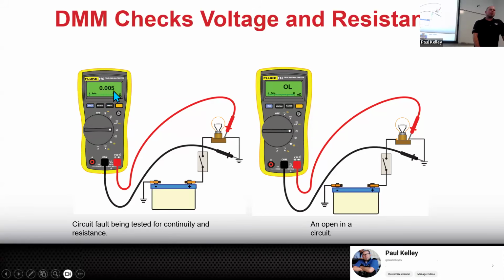So if you look at this, that's pretty much 0. You've got not a tenth, you've got a half of a nothing there. That wouldn't even show up typically on the meter, so you're good - that has 0 volts after. Coming into it, you should have source voltage of 12.6, and we'll show that, but this would be using the meter to check available voltage. You could pretty much diagnose any circuit you need with just available voltage, so we'll focus mainly on that.